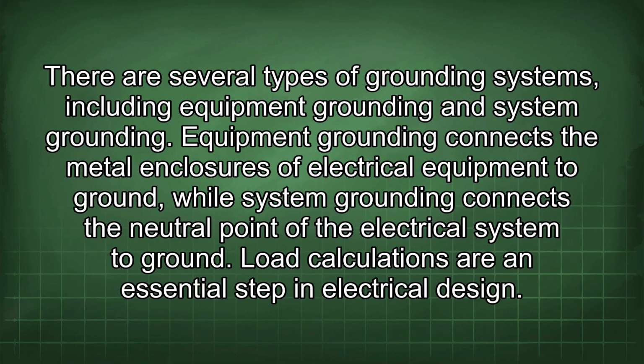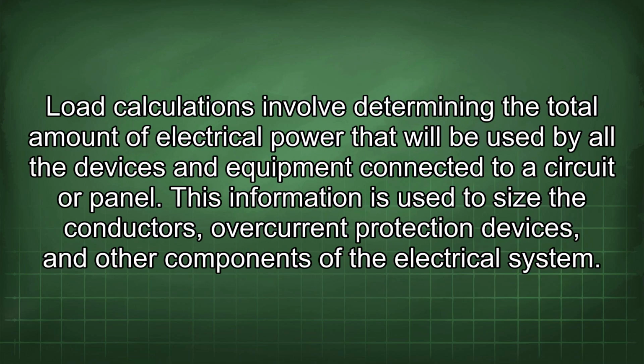Equipment grounding connects the metal enclosures of electrical equipment to ground, while system grounding connects the neutral point of the electrical system to ground. Load calculations are an essential step in electrical design. Load calculations involve determining the total amount of electrical power that will be used by all the devices and equipment connected to a circuit or panel. This information is used to size the conductors, overcurrent protection devices, and other components of the electrical system.